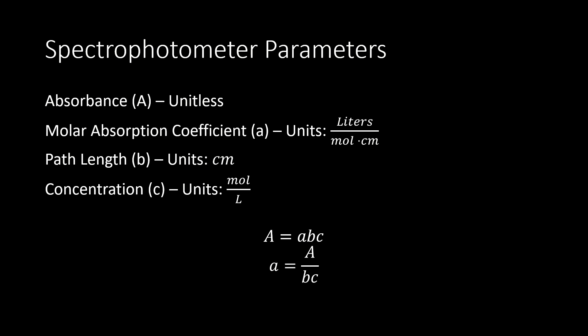Getting into the spectrophotometer parameters specifically, there are four main ones related in the following way. Absorbance, which is unitless, equals the product of the molar absorption coefficient, the path length, and the concentration — A = abc. The molar absorption coefficient, sometimes called the molar extinction coefficient, depends on the type of ion we're looking at. Little a is the molar absorption coefficient, little b is the path length, little c is the concentration, and capital A is absorbance — what we directly see on the spectrophotometer.